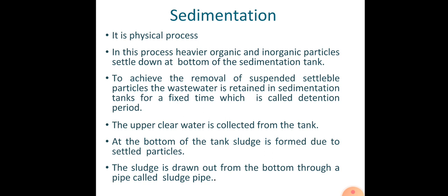After water is kept for a particular detention period, and after all the particles settle down to the bottom, the upper clear water will be collected into another tank, where the further processes like filtration and disinfection will be carried out, and the sludge that is settled at the bottom of the sedimentation tank will be removed. This is usually drawn out from the bottom through a pipe.